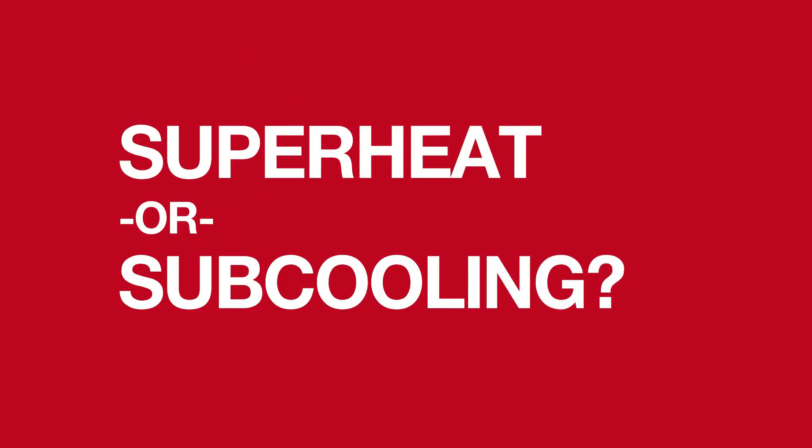When troubleshooting a piston-driven system, what will you use to calculate your charge — superheat or subcooling? The answer is superheat. The reason you want to use superheat to calculate your charge is you want to know the state of refrigerant in the evaporator coil.